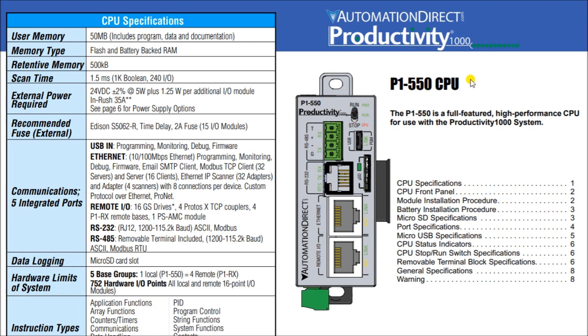So the capabilities and this tag-based system are identical except for the P1550 will allow remote I/O capabilities. And what this will allow you to do is connect up to 16 GS drives with the communication module, up to four P1RX remote bases, so that's basically more expansion cards for the Productivity 1000 line, and four Protos X TCP couplers.